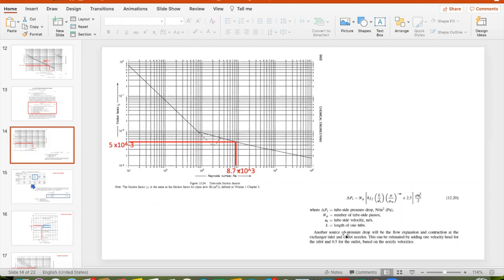Another source of pressure drop will be the flow expansion and contraction at the exchanger inlet and outlet nozzles. This can be estimated by adding one velocity head for the inlet and 0.5 for the outlet, based on the nozzle velocities. That is another factor we might need to take into account, and we will do so later in the next step.